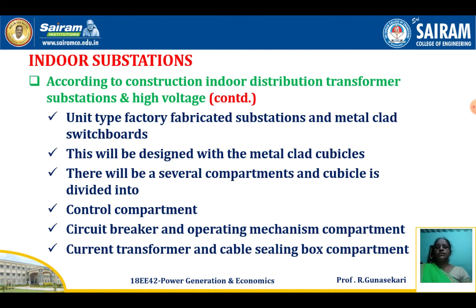According to construction, the indoor distribution transformer substations and high voltage switchgear units are designed with metal clad only. Then there will be several compartments: a control compartment, a circuit breaker and operating mechanism compartment, and a current transformer and cable sealing box compartment also.